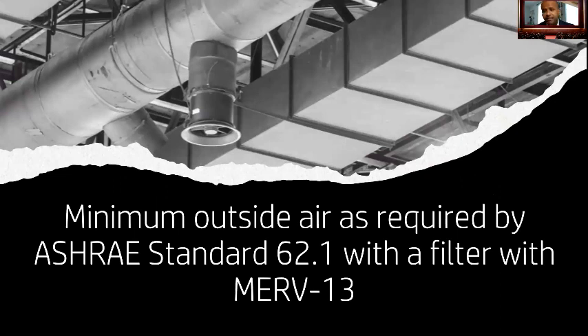If there are significant energy impacts from increasing outside air for ventilation, ASHRAE recommends using a minimum outside air per ASHRAE Standard 62.1 along with a MERV 13 filter. MERV stands for minimum efficiency reporting value. We'll talk about filters in a bit. Now, one may argue that with MERV 13, your HVAC system will have to push harder with the pressure drop. It is true, but what I've seen from recent studies is that the MERV 13 pressure drop is comparable to MERV 8, or not significantly high.